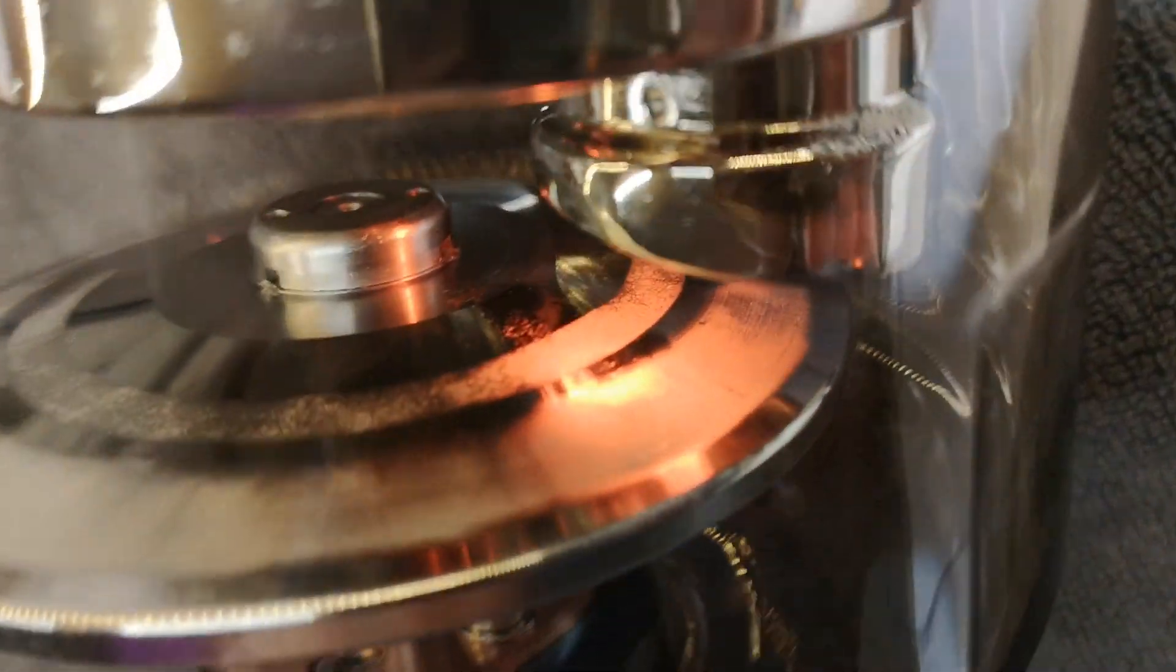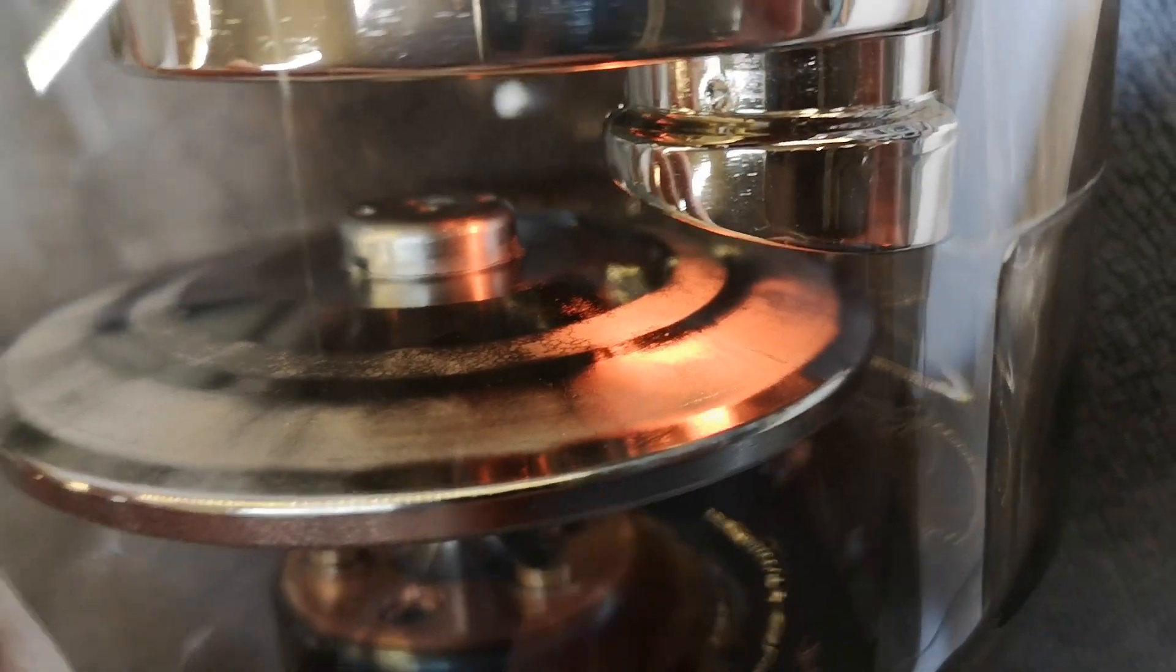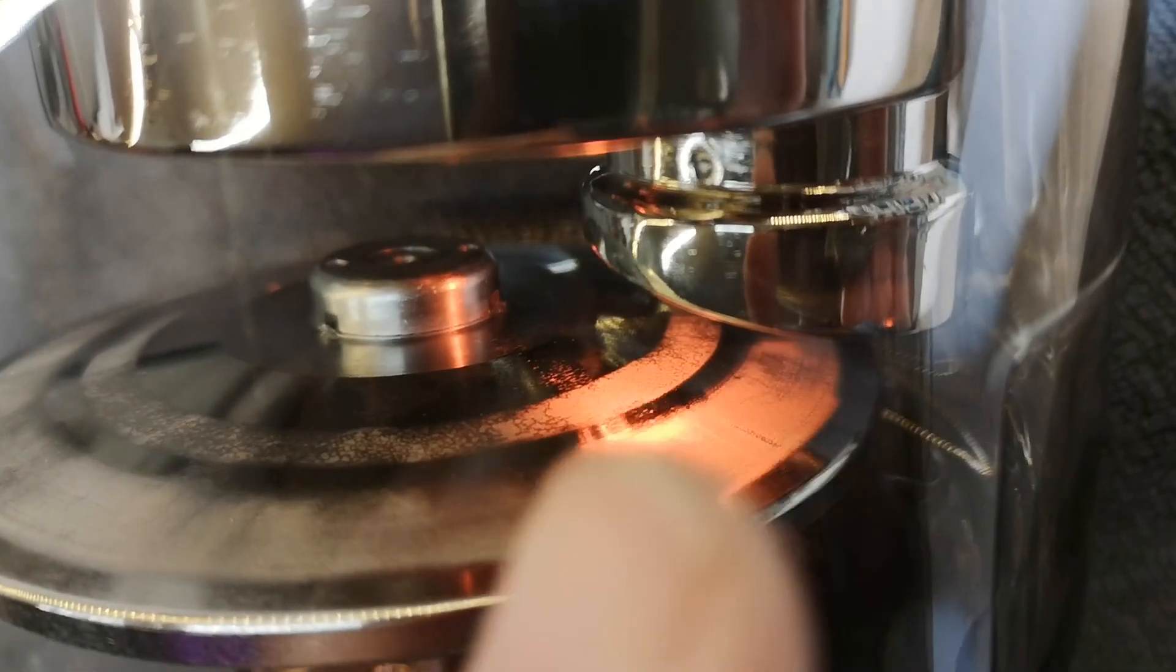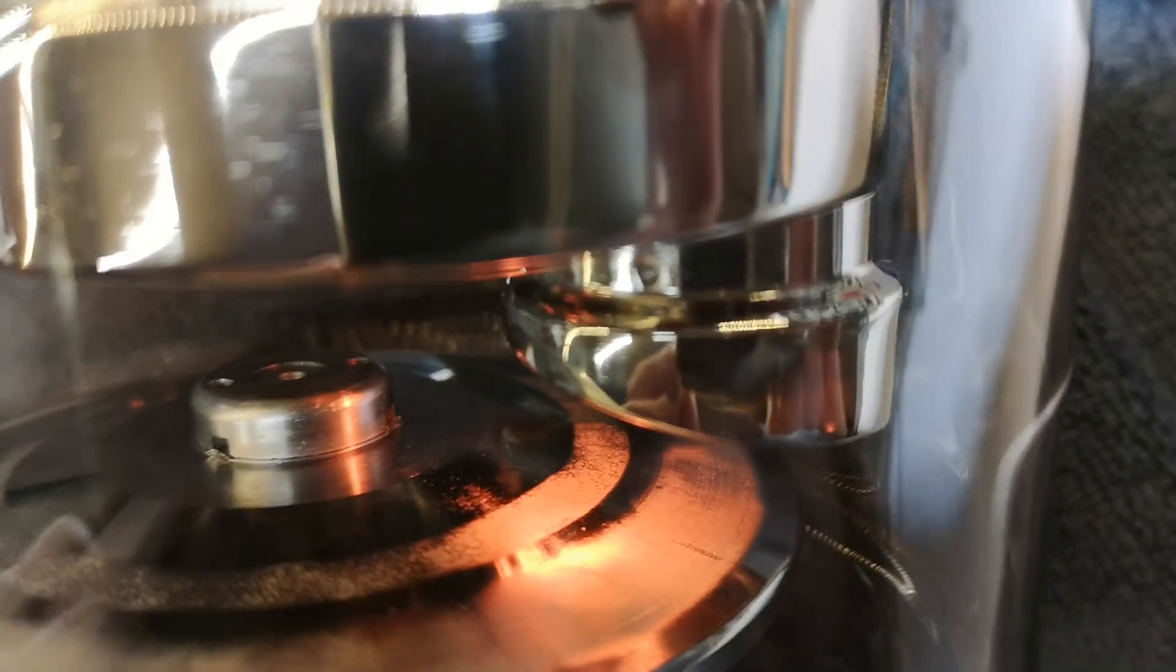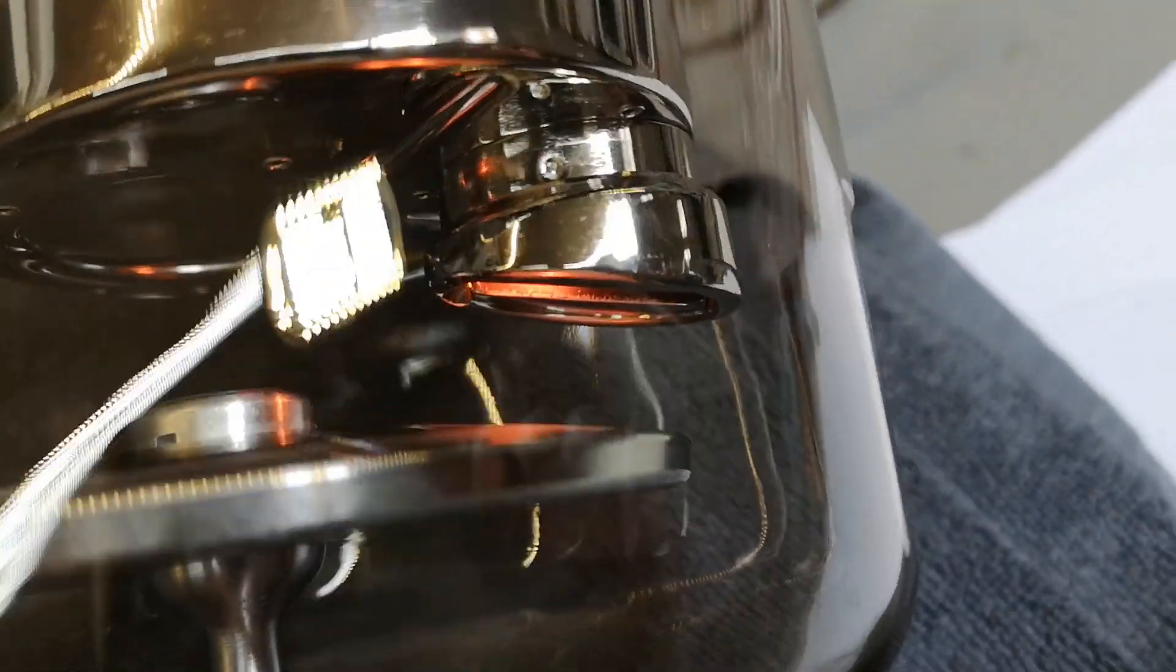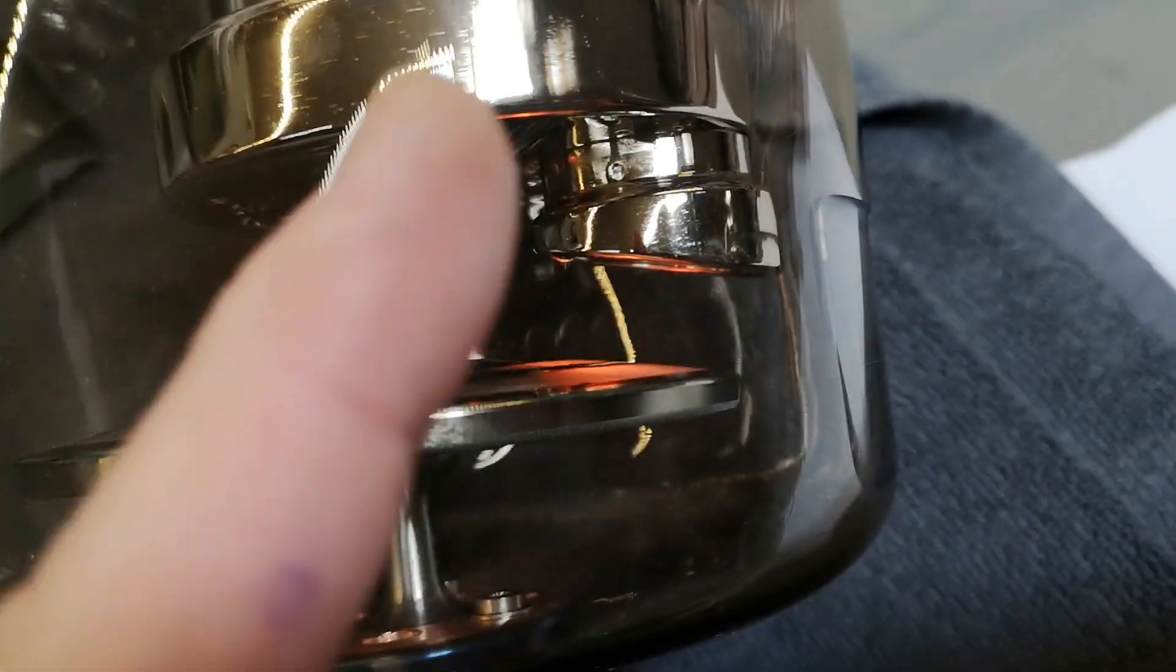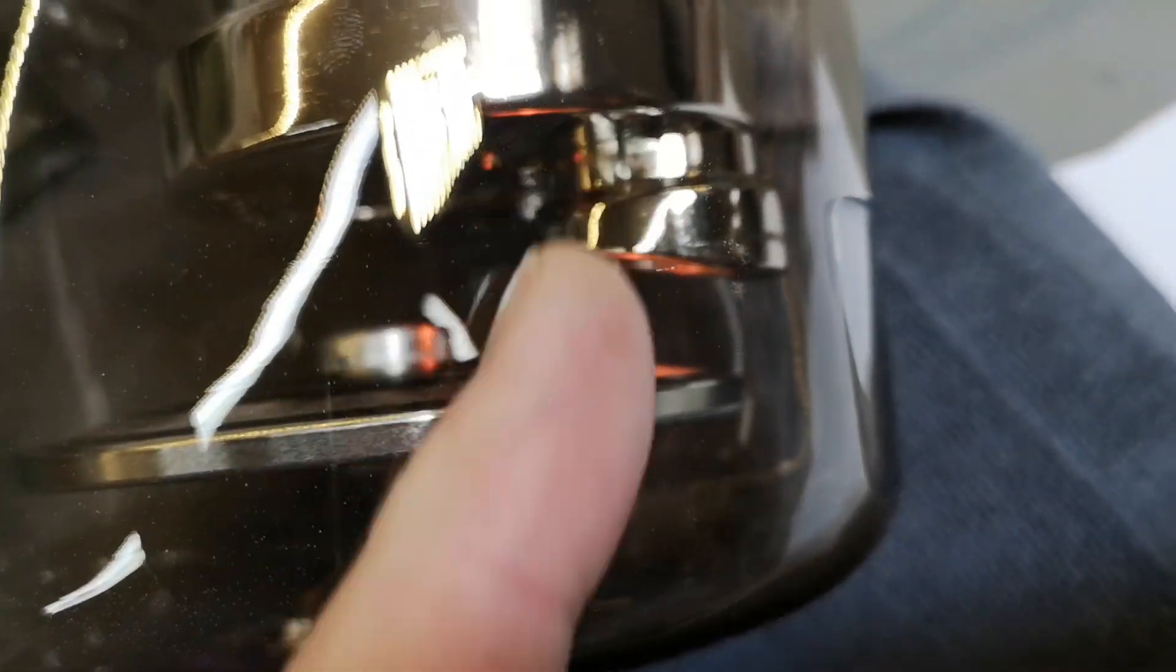You can also see on the wear on the anode, so that will be the small beam or the narrow spot. This is where it's going to hit, and if you look at the angle it's made, it's actually hitting here.